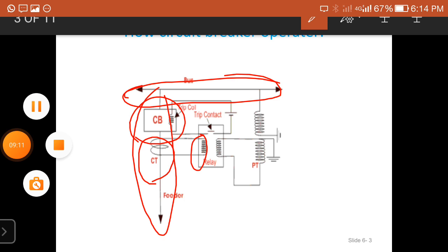This is the basic diagram for working of a circuit breaker. The basic construction of a circuit breaker requires separation of contacts in an insulating fluid and serves two functions. The first one is to extinguish the arc drawn between the contacts. When the fault is obtained, the moving contact moves away from the fixed contact. Then the arc is struck in between the contacts of the circuit breaker. Next, it provides insulation between the contacts and from each contact to the earth.